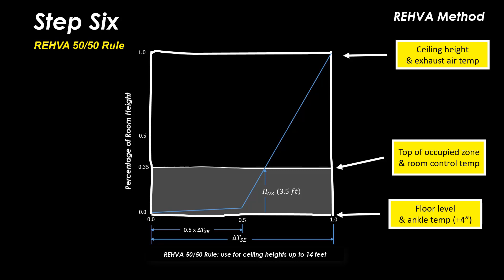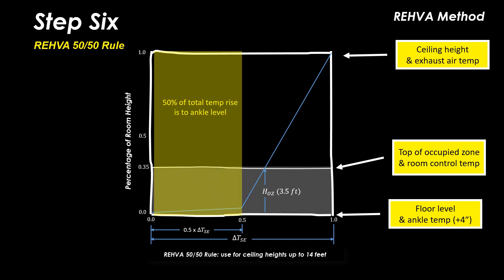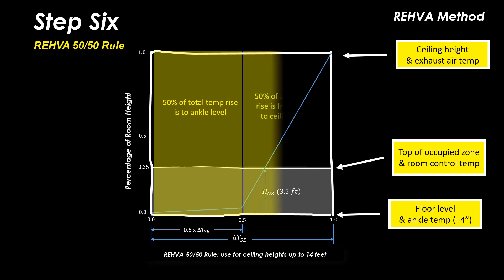The 50-50 rule estimates that the space vertical temperature gradient makes up half of the total supply return temperature differential between the supply outlet and ankle level, and the remaining half between the ankle level and ceiling.